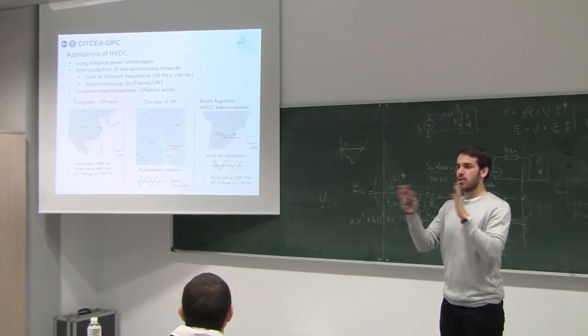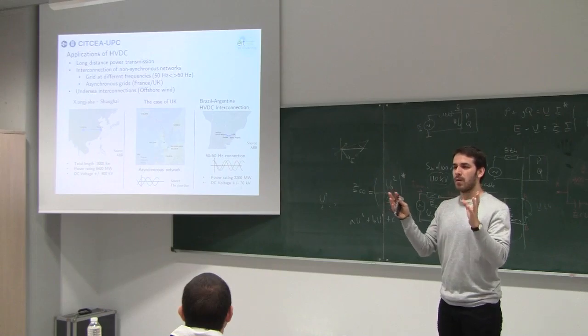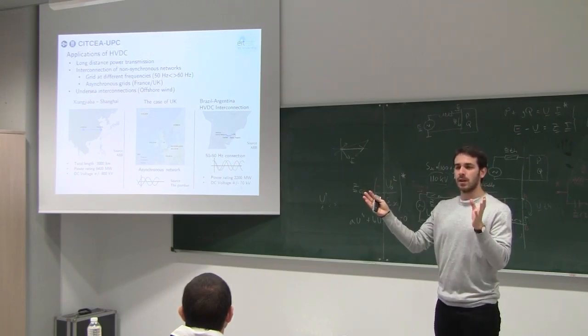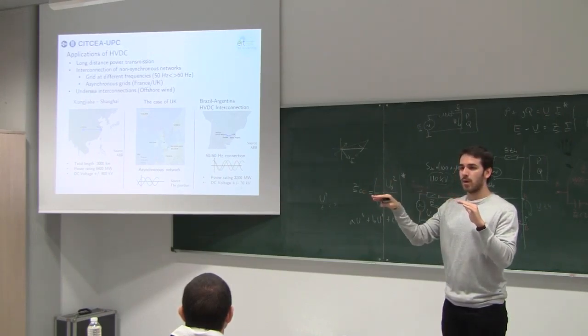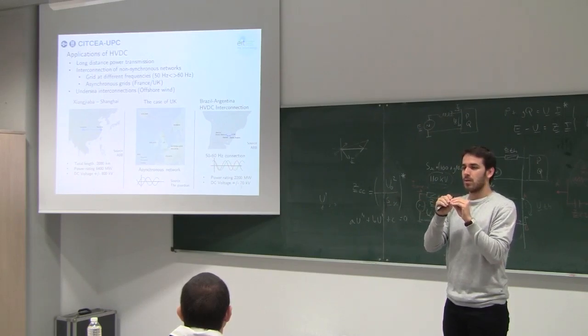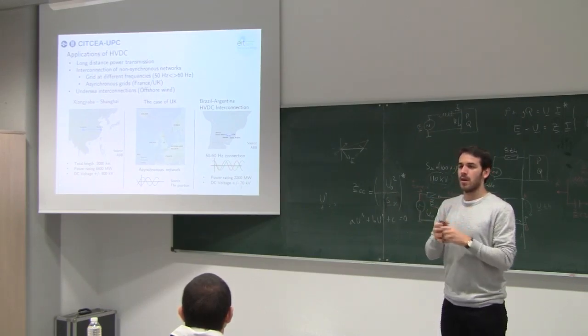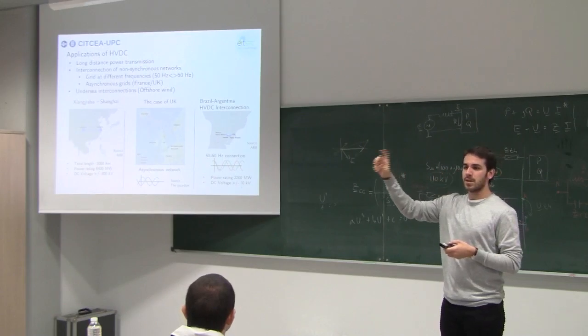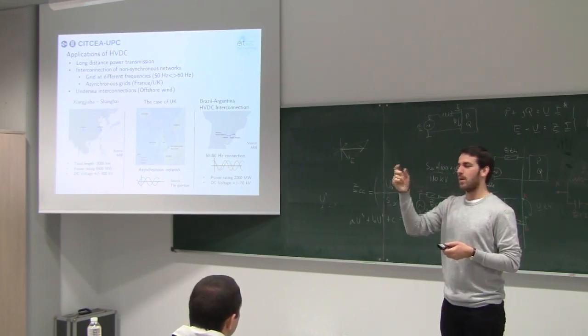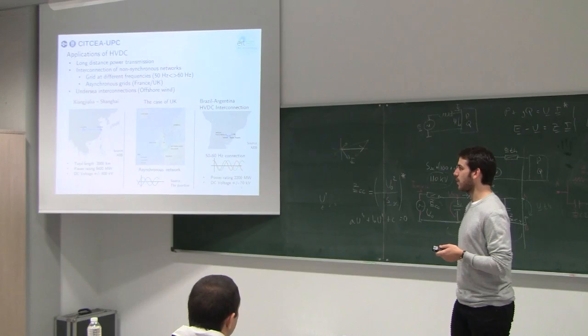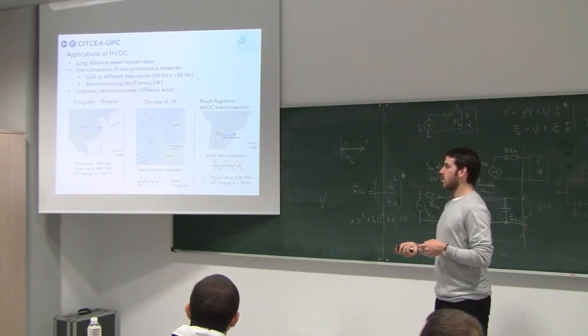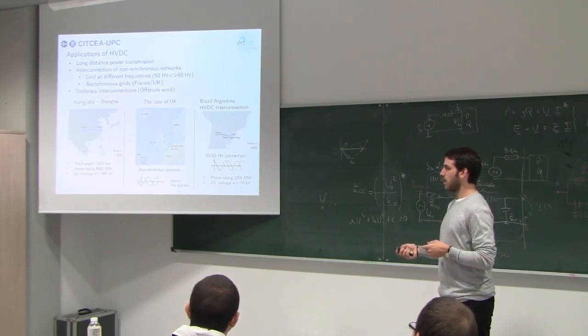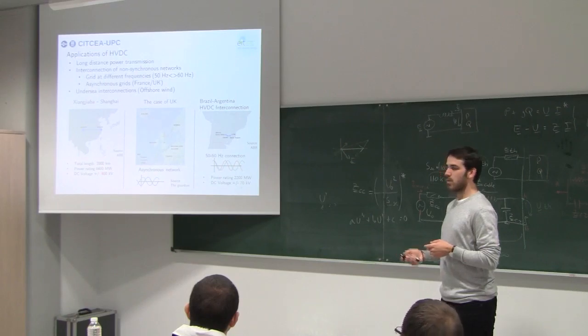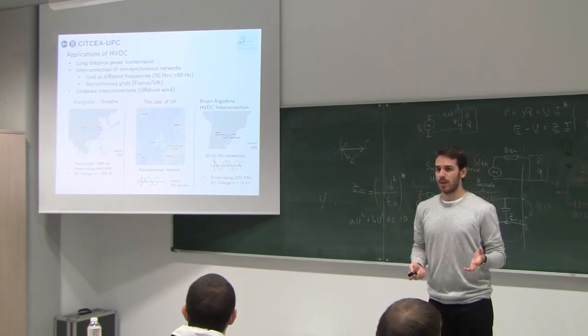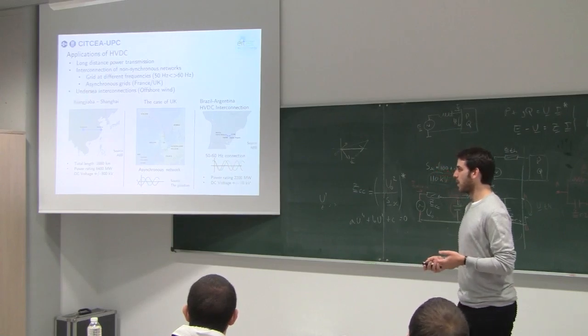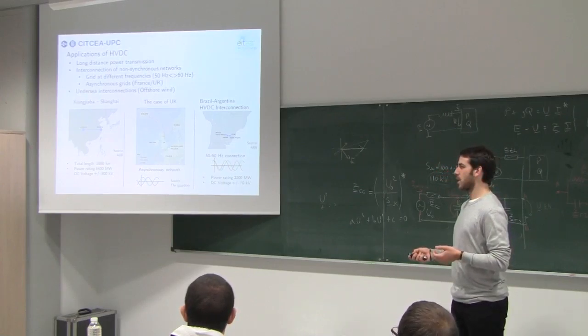Due to the reactive power, if we have done that in AC, just the reactive power losses, it won't be technically possible, unless we are compensating this reactive power with capacitor reactors or whatever. So that's something that has been done by ABB in DC. The power rating is 6.4 gigawatts, so it's quite a lot of power going through this line, and the DC voltage is plus minus 800 kV.